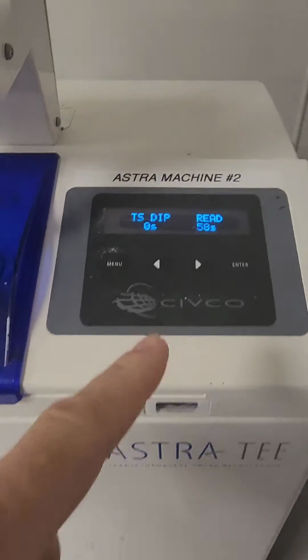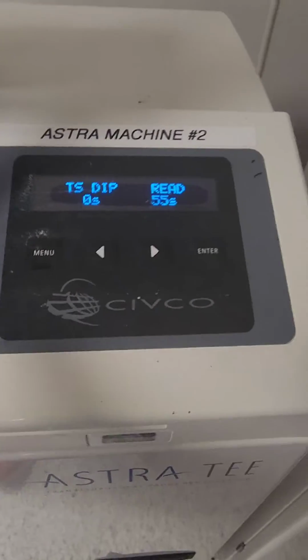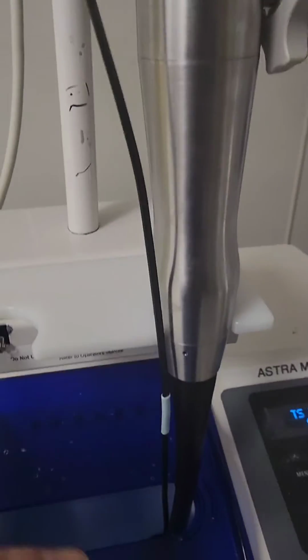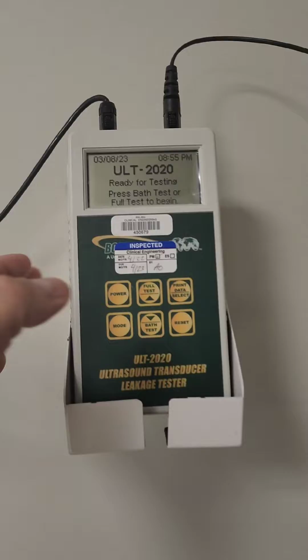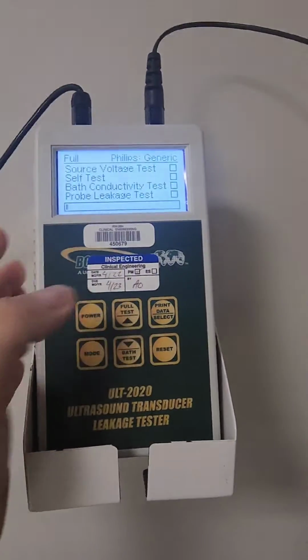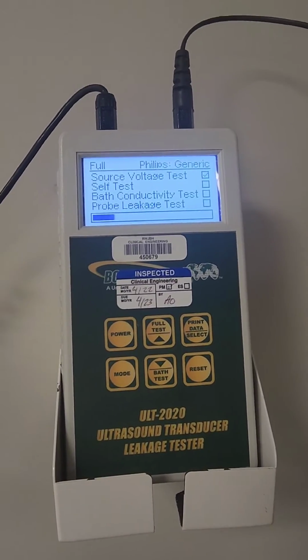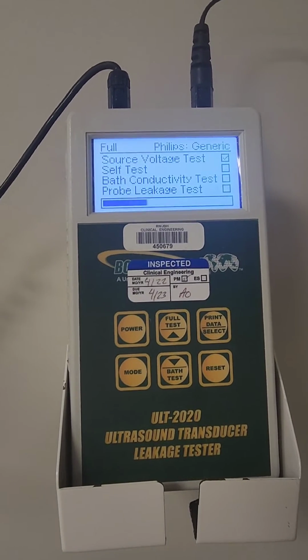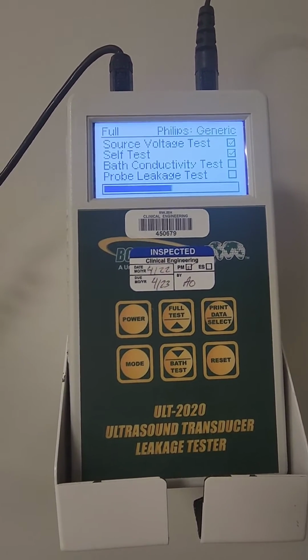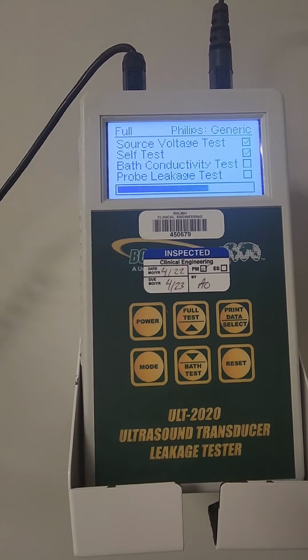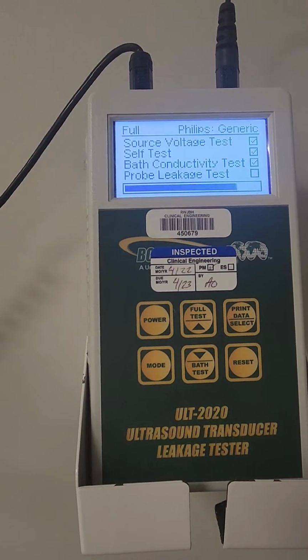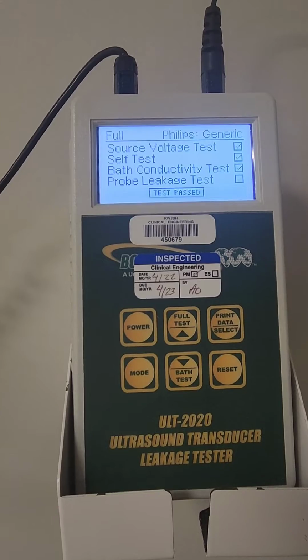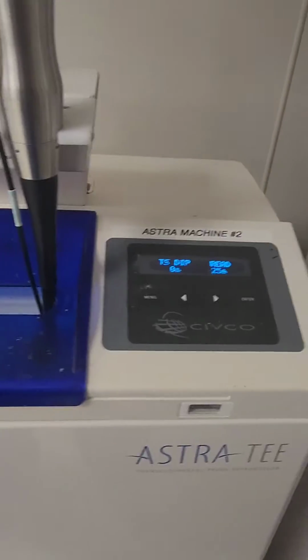So you see that the countdown is on there. I'm at 56 seconds for my test strip, and then I'm about to leak test this scope. You put the probe down in one of the chambers there. I already had the settings in there, and there you go with the leak testing. It does several tests: it tests the conductivity of the solution, the voltage in the battery, and then the probe. So that passed right there.